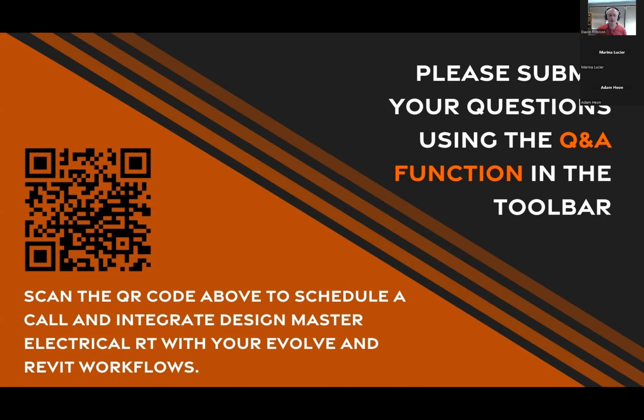Question on the feeder lengths. All the feeder lengths, we're pulling from the location of devices in the model. If you move pieces around, we recalculate for them. You can show them on the one line as well. I'm not sure what your question on the feeder lengths is, but if you take a look at this feeder, we have the length specified here, somewhere in here. It's currently pulling 0 because it just got put in and hasn't been recalculated. If we go to this one, we've got the circuit length being displayed there.